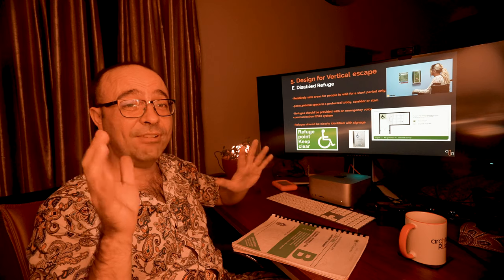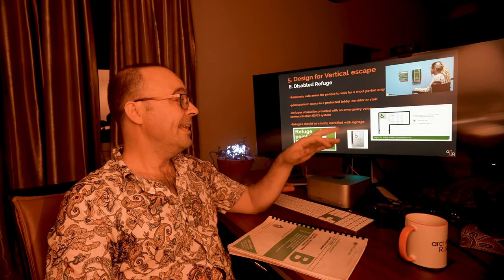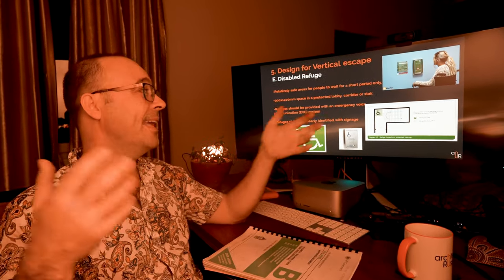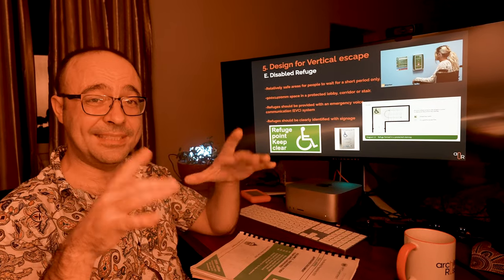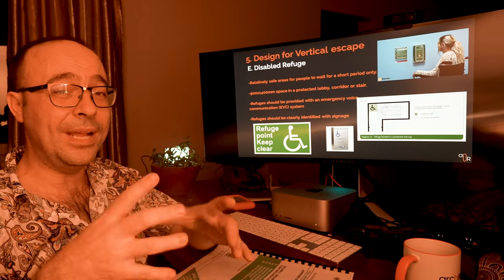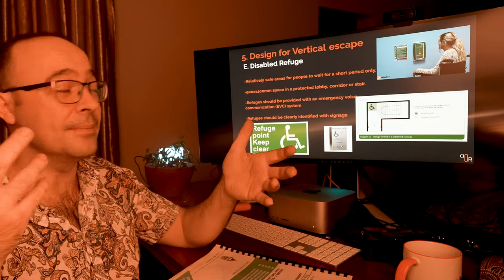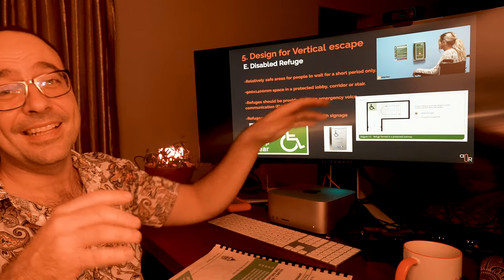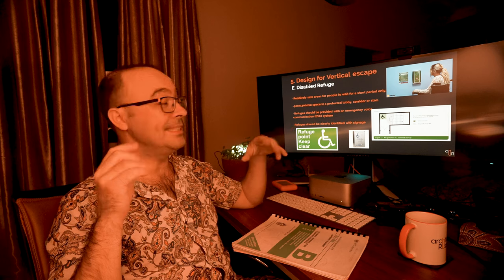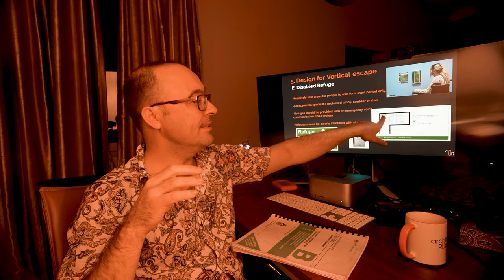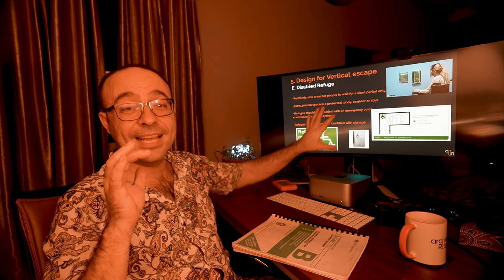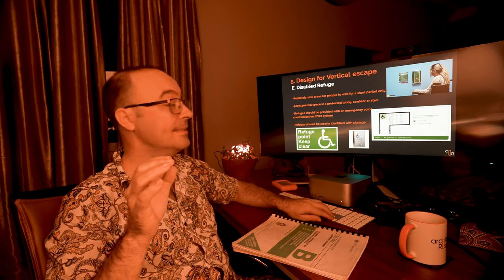Now onto disabled refuges — this is important; a lot of people miss this out. In an escape stair or a protected area like a lobby, you've got to have a disabled refuge: a safe area where people with disabilities can go and call for help and wait until the fire brigade comes. It's got to have a call point that allows them to call for help. The size is 900 by 1,400 millimeters, and it can't block the route of escape — it's got to be kept away from the flow of traffic for the stair. You've also got to put signage there to allocate that space.